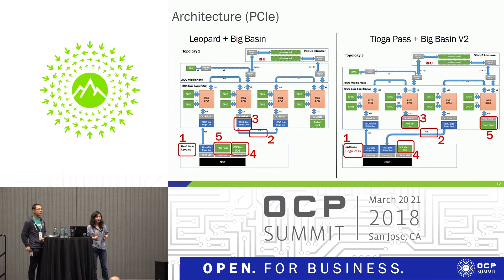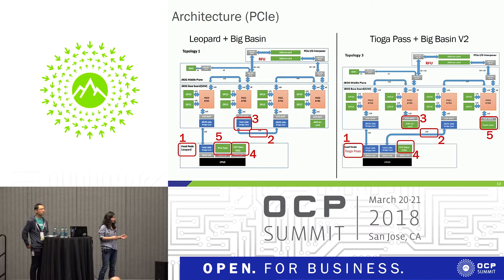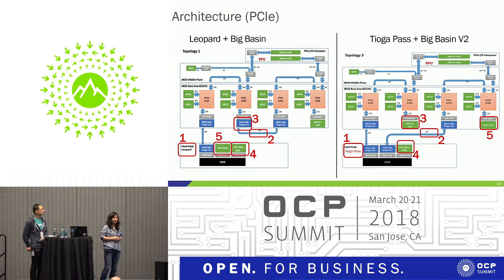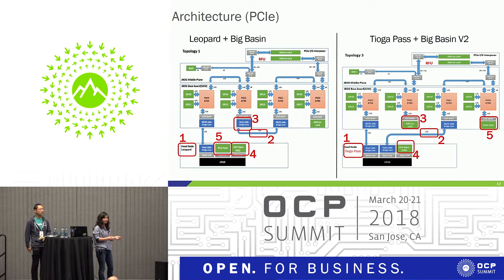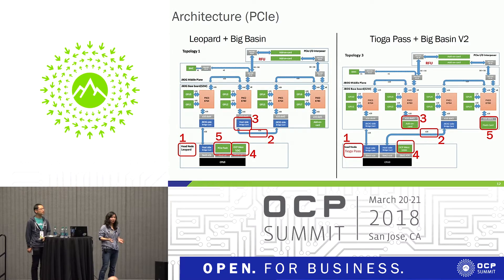This change affected the PCIe enumeration bus number. But for Big Basin V2, since we have a fixed configuration, our BIOS can fix all resources and bus numbers for each device. This means that if a device fails to boot or be recognized, the PCIe bus numbers of the remaining devices will not change. Our software tool can then easily compare against a golden config file to identify exactly which device is missing, and pass this information to our data center techs for quick repair. From a serviceability standpoint, we are also improving firmware and software alongside hardware.